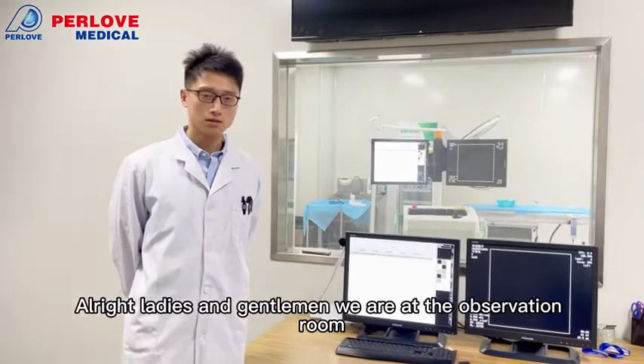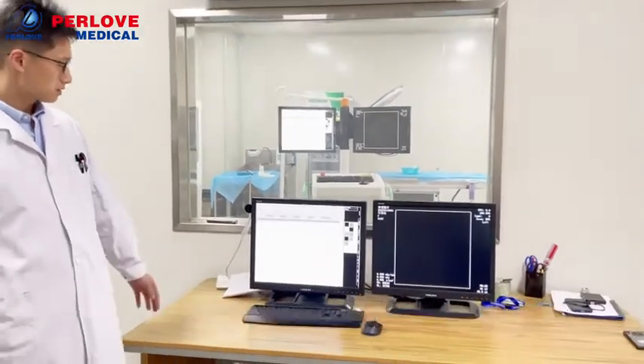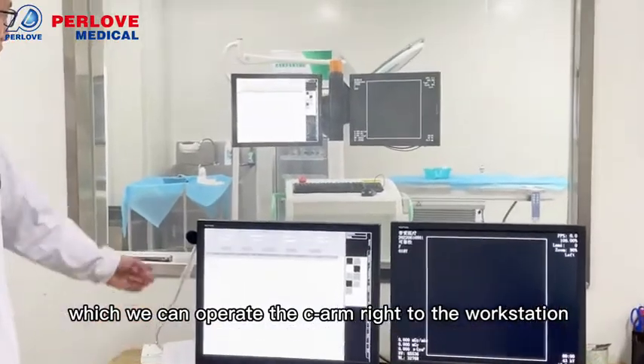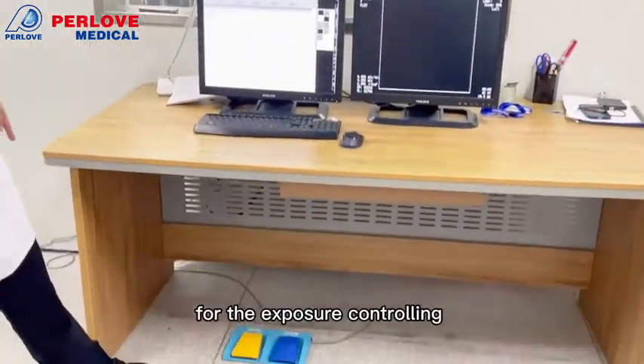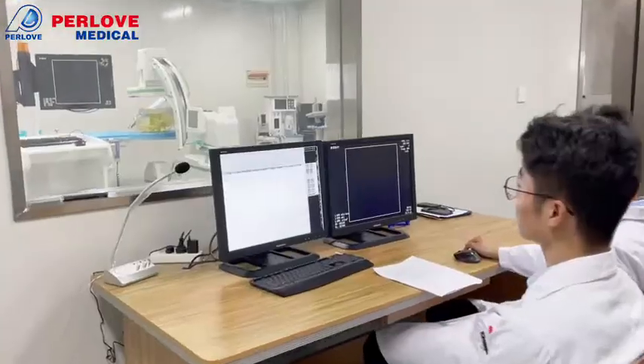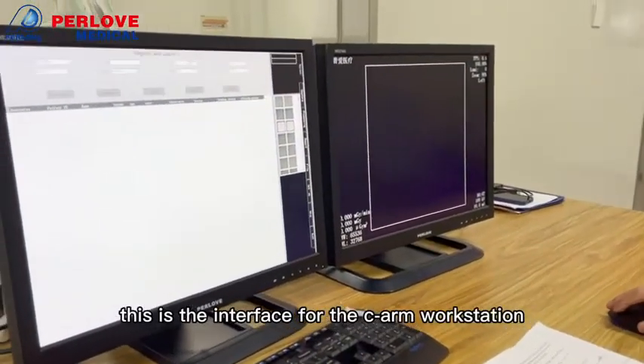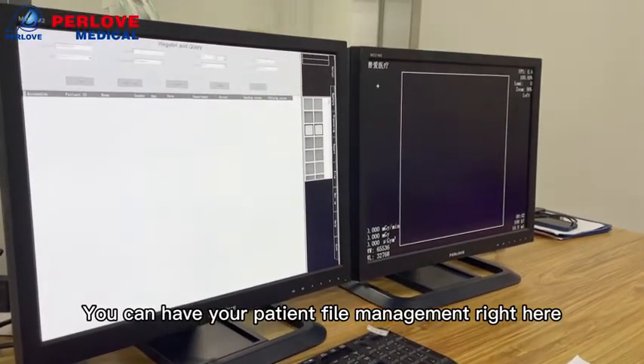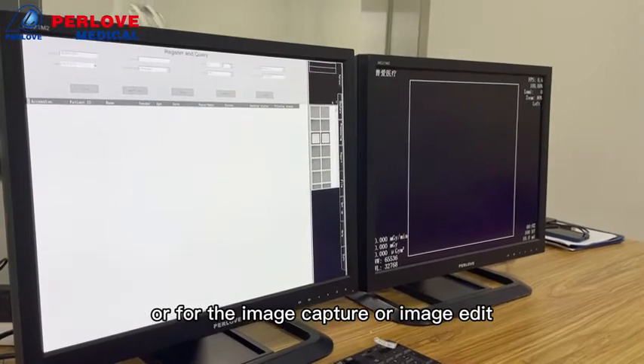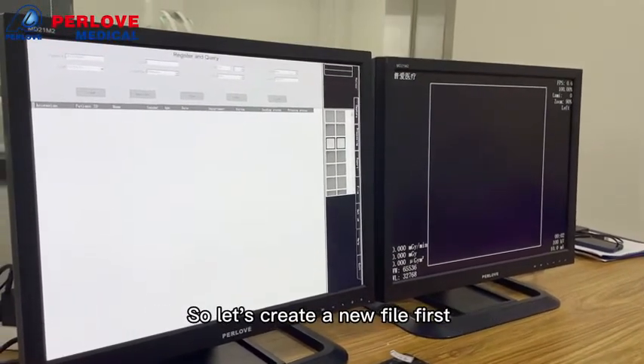Alright ladies and gentlemen, we are at the observation room. You can see we have two extension monitors right here, which we can use to operate the c-arm right at the workstation. We also have a foot switch for the exposure control. This is the interface for the c-arm workstation — you can have patient file management right here, or for image capture or image editing. So let's create a new file first.